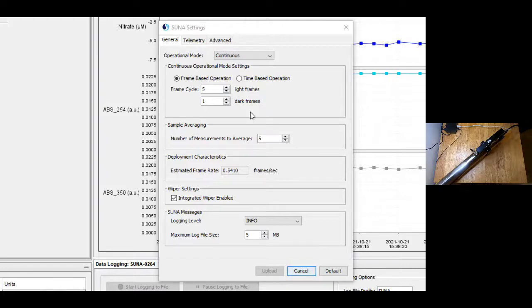You can do a number of measurements to average. I do always recommend averaging, unless you're really looking for something, if you're looking for the performance. If you're actually sampling in the field, I always suggest averaging because it does take down the noise a lot. That could be confused with the real signal, and it does actually help your instrument be more accurate. If you are doing troubleshooting, typically I actually will take 1 sample to average and I'll go down.